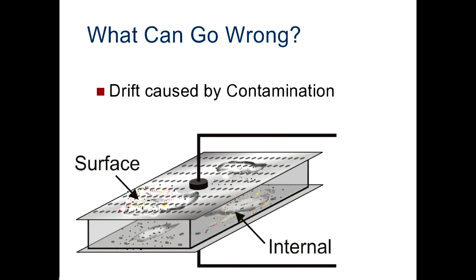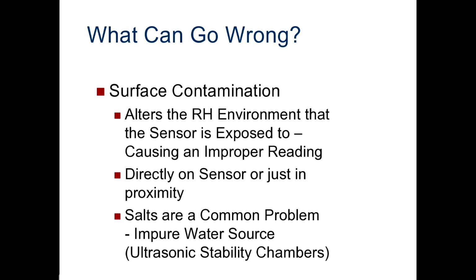Well, what can go wrong with a system like this? Drift or measurement errors can be caused by surface contamination or internal contamination. As we said earlier, the humidity sensor's internal structure is exposed to the environment, so it is subject to contamination from the environment. Surface contamination actually alters the relative humidity near and on the sensor itself. So although the sensor may be measuring accurately, the environment it sees right around it is not a true representation of the greater humidity environment, causing an improper reading.